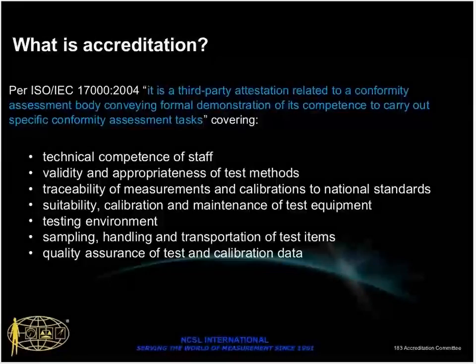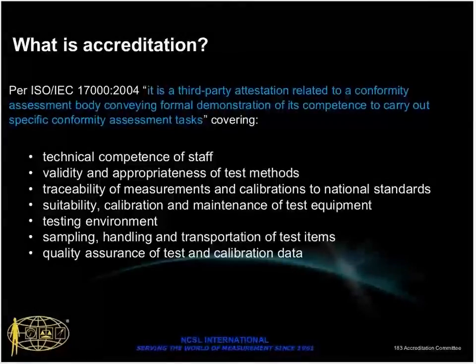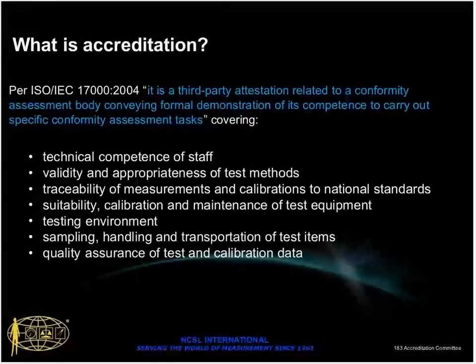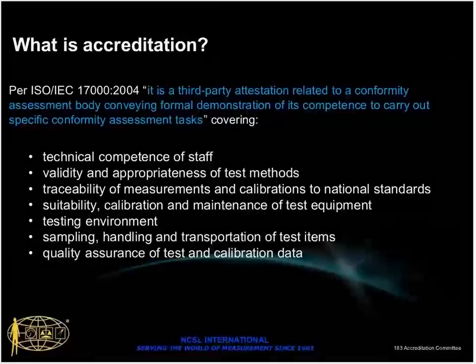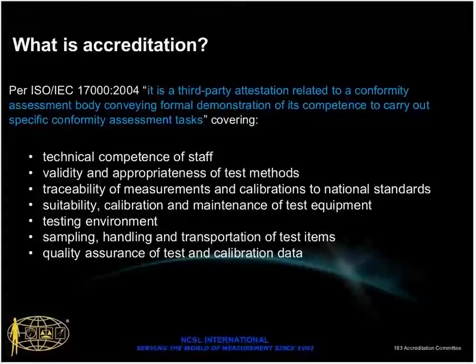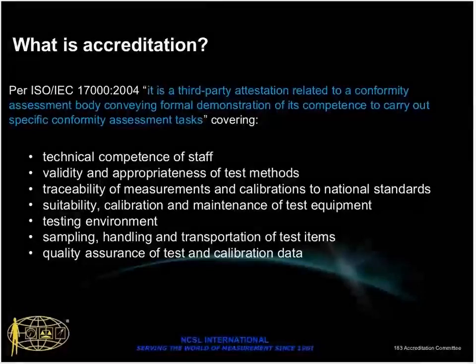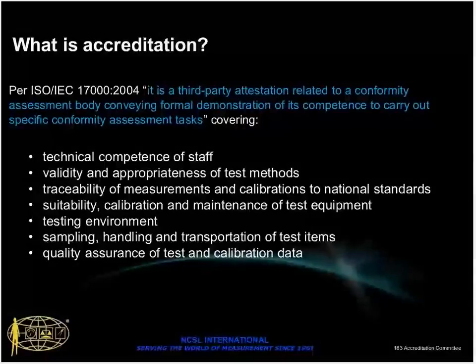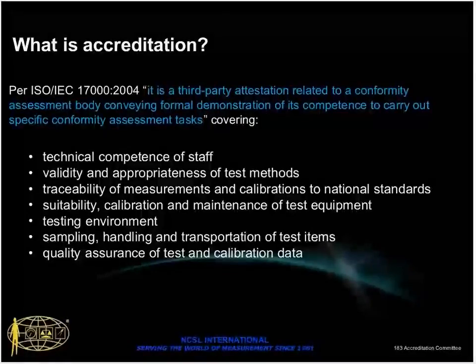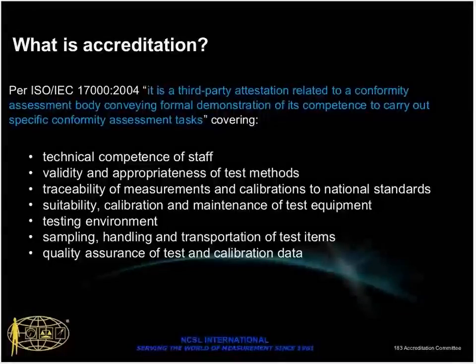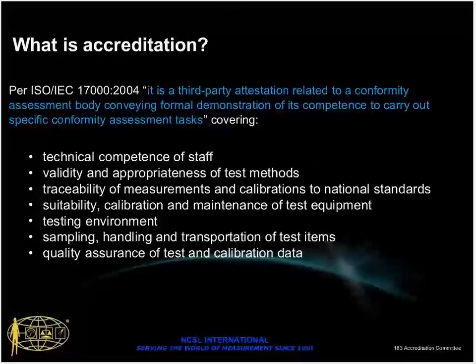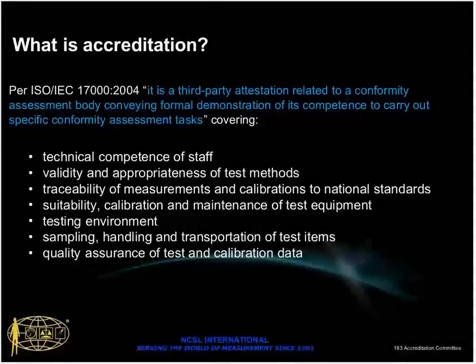But looking at the definition and breaking it down into simple terms, what it's basically saying is that accreditation bodies are sending out qualified assessors to the laboratories to perform an assessment of not only the quality system but of the scope of accreditation, covering these bullets here that we see on the screen. So the assessors are reviewing the technical competence of the staff, the validity and the appropriateness of the test methods, traceability of the measurements and the calibrations to not only national standards but international standards, the suitability, calibration, and maintenance of the test equipment, what kind of environment the calibrations are being performed in, what requirements are in place for sampling, handling, and transportation of the test items or the equipment, and what I would consider the most appropriate aspect of the accreditation, ensuring that the quality of the test and calibration data is sufficient.